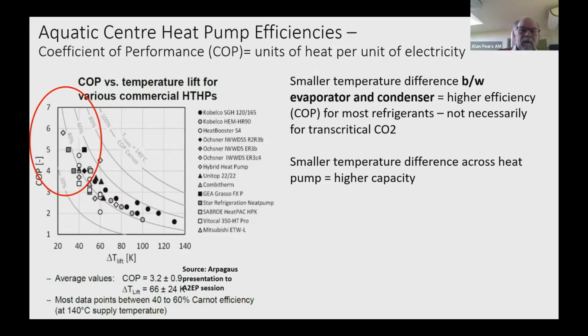But again, there's an important message in this graph, which is you can see the smaller the temperature difference that the heat pump works across, the more efficient it is. And once you're starting to get down to quite small temperature differences, like heating water by 20 degrees or 40 degrees, you can see that it is typically running at 400% to 600%, 700% efficient. And that's the sort of space that a pool heat pump should be running in if it's well designed. Now, I should emphasize that the transcritical carbon dioxide refrigerant heat pumps don't quite work this way. They are a bit quirky, and I don't have time to go through them, but they're pretty different, and they need a whole lot of other attention.